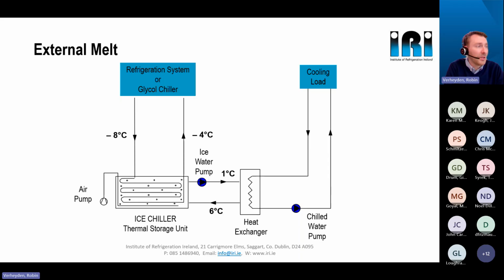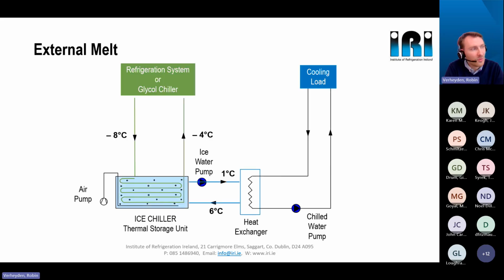A typical schematic for external melt is this one. And here you will already see a slight difference from internal melt. With internal melt, we are using the same coil. It's generally easier to install. With external melt, you have two loops. On the left side, you have the loop to build the ice. So the refrigeration or the glycol chiller is connected to the coil with standard, a little bit lower temperatures, -8 to -4. And on the right side, you will see the cooling load, now directly connected to a pump that will force water going through or over the ice block in the tank. So two separate loops.